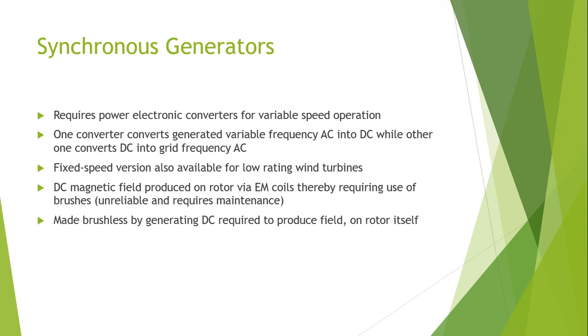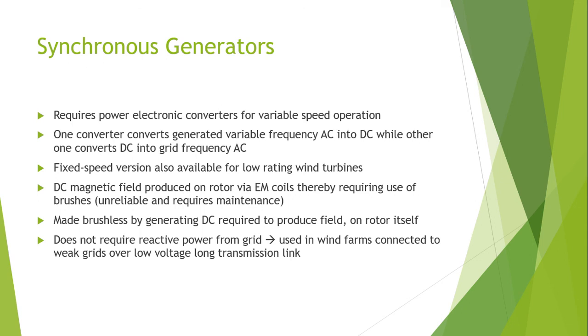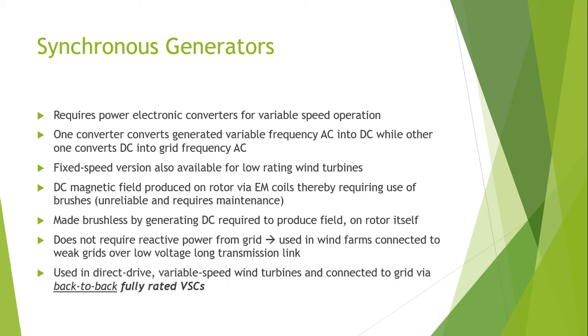Synchronous motors and generators in the modern era are made brushless by generating the DC required to produce the field on the rotor itself. It does not require reactive power from the grid, and is used in wind farms connected to weak grids over a low voltage along a long transmission line. Also, they are used in direct drive variable speed wind turbines, and they are connected to the grid via back-to-back fully rated voltage source converters.